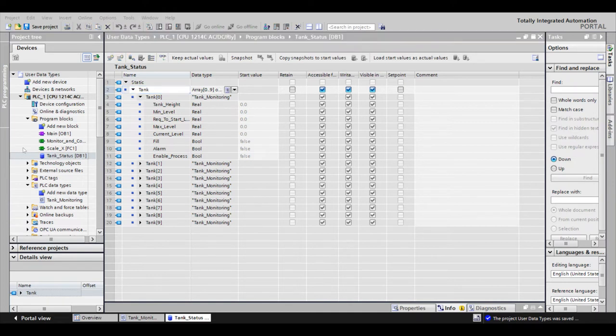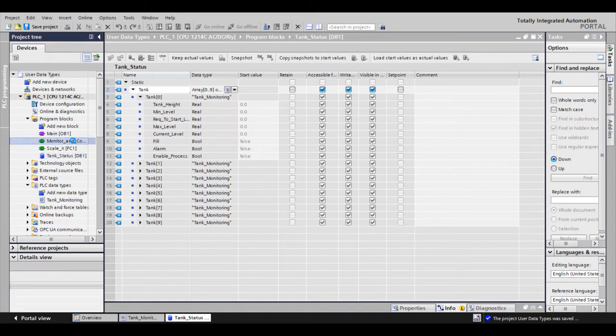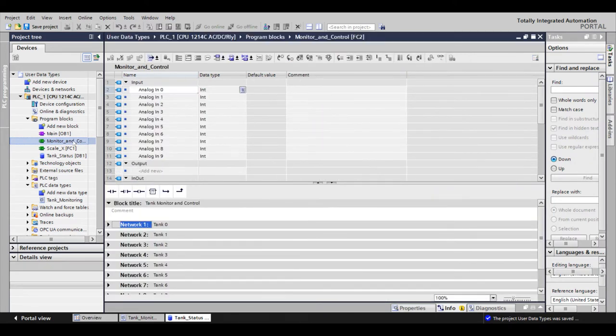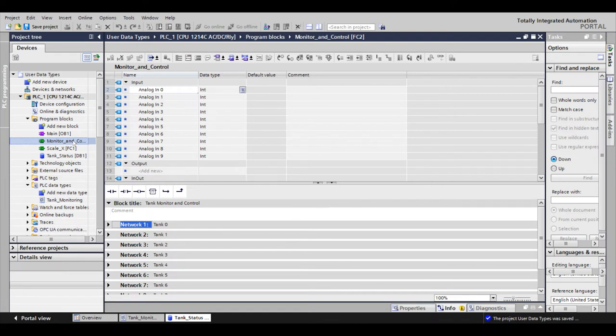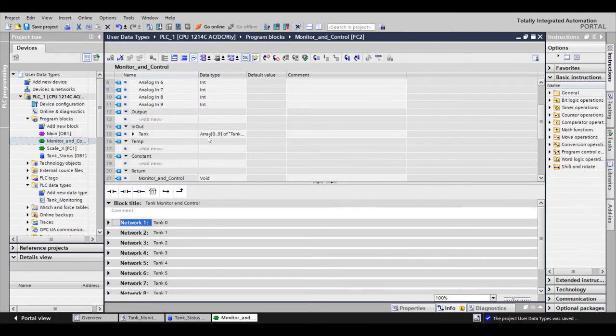Once I created the data block for our UDT, I created the logic. Now I won't show you the logic itself, but I will show you the interface because that's how we pass through parameters to our function. Here at the top, you have the analog inputs for your 10 tanks. And then down under in-out, we have the data block array for tank control.